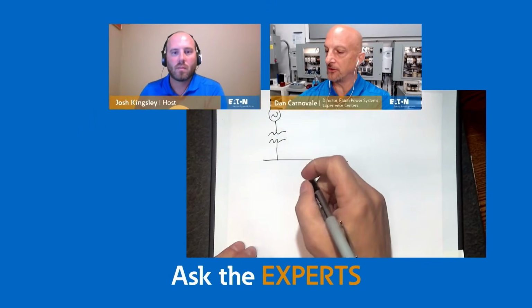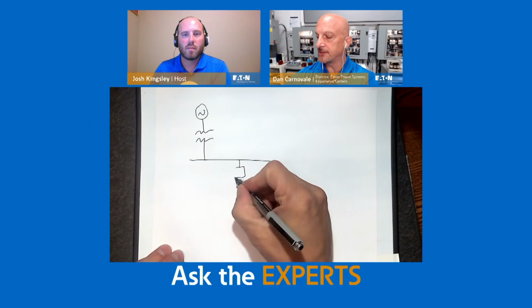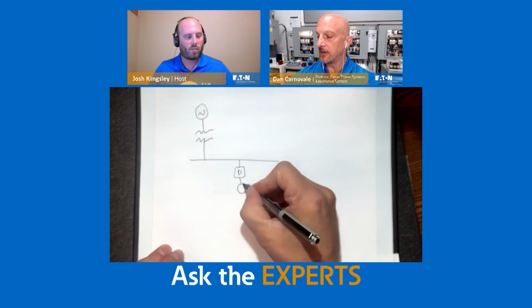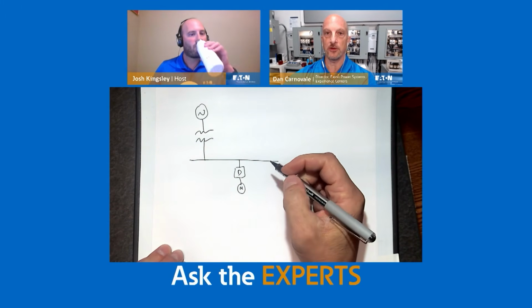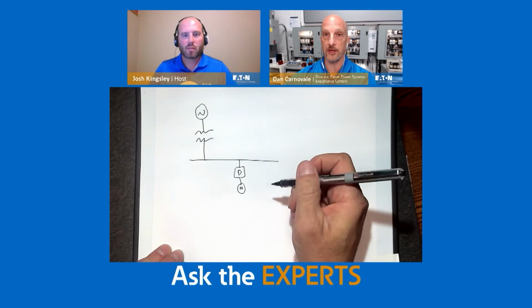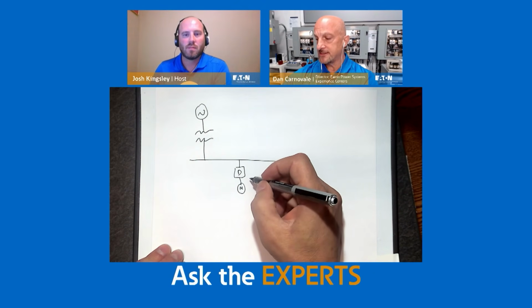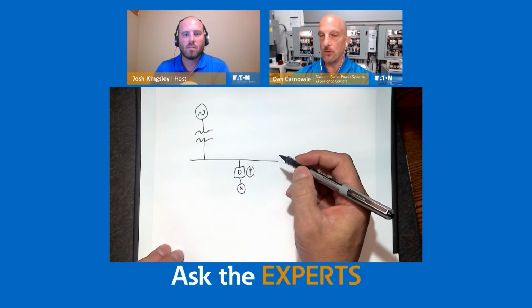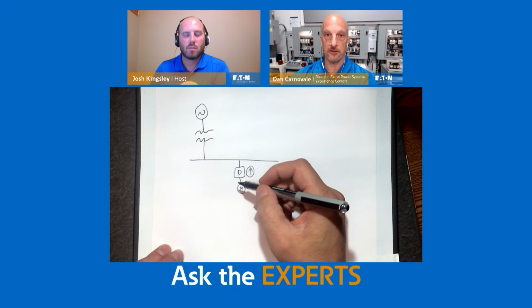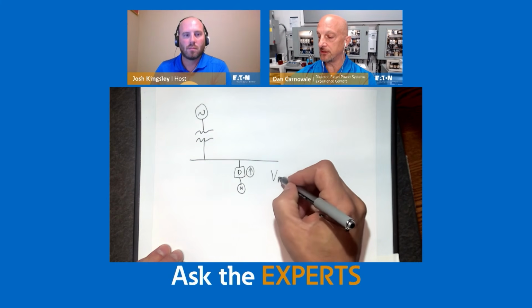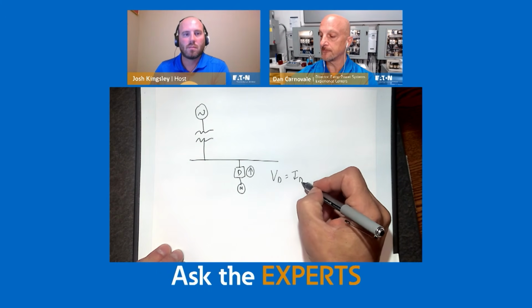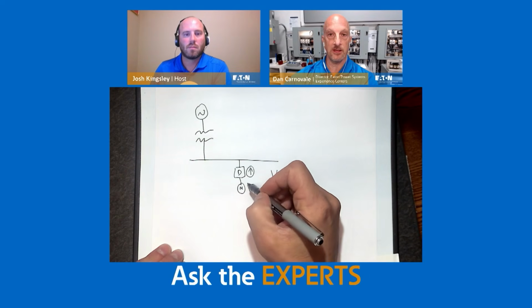What are the key harmonic solutions for VFDs, and how do you decide which one to pick? That's a great question because, if you think about it, as I mentioned, I have to use the drawing tablet here. If I put my drive on here, and I say that I have harmonics coming out of my drive, and I'm simplifying this, obviously it could be multiple drives, it could be multiple different harmonic loads, whatever they happen to be. But as that current comes out of the drive and it wants to go somewhere, we have to either find a new path for it to go through that's a lower impedance, going back to that voltage distortion equals current distortion times harmonic impedance, or we can actually limit that current from coming out.